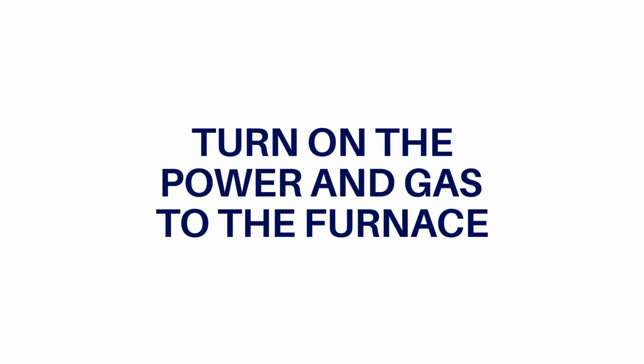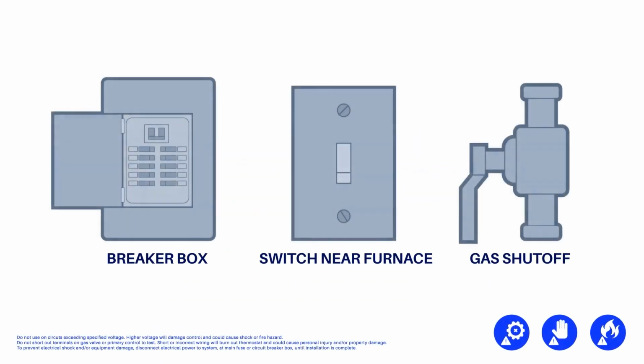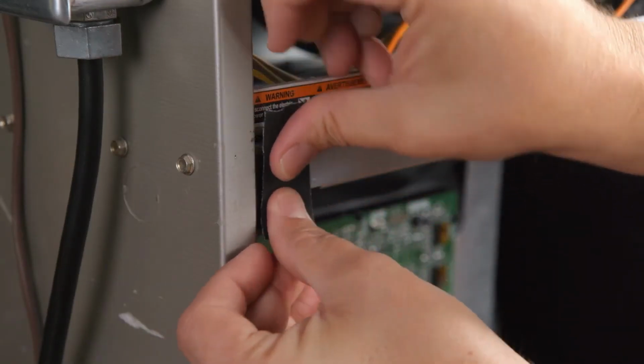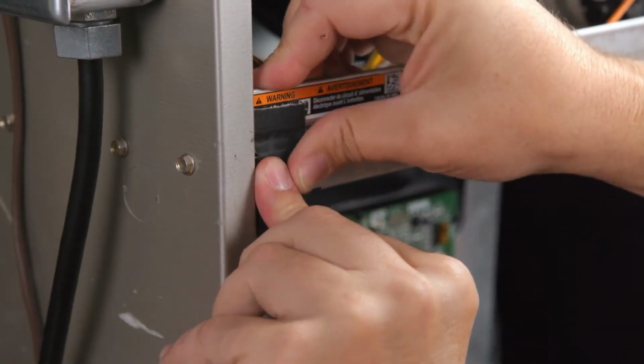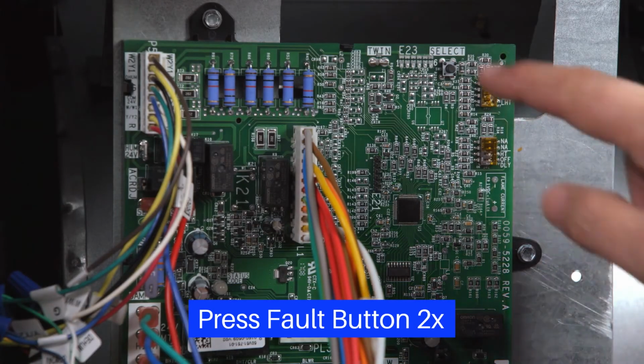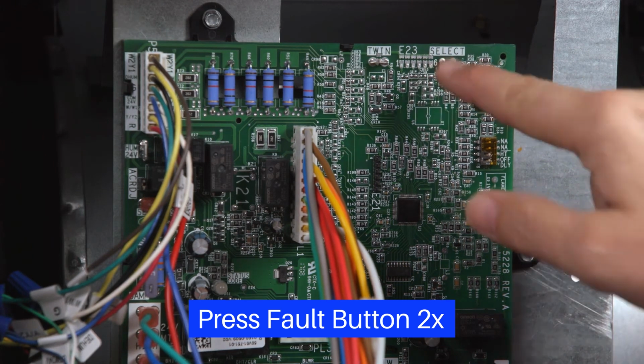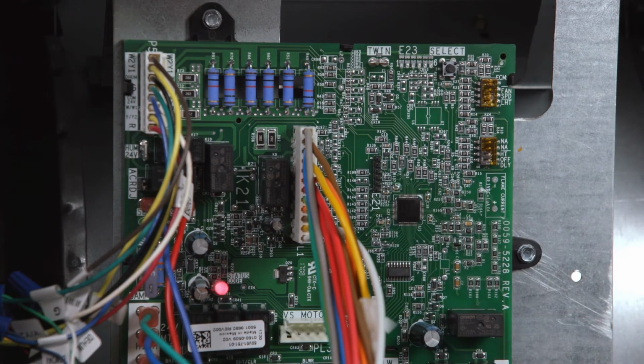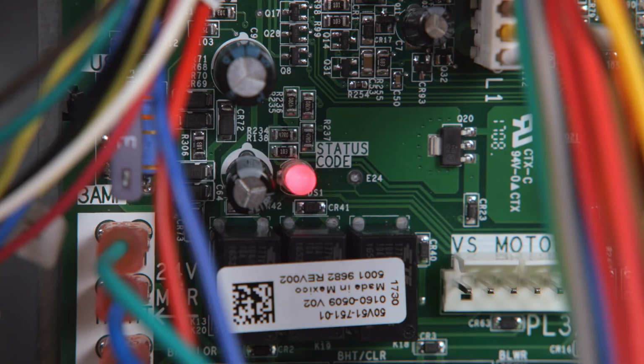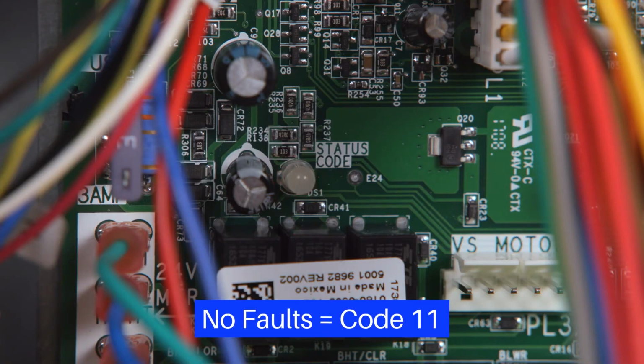The system is now ready to be tested. Reconnect electric power and gas to the unit. To enter self-test mode, turn on power and ensure the door switch is engaged. Press the select button twice within 3 seconds after powering the control. If there are faults, the control LED will flash in red the last error code only. It will do this 4 times. If there are no faults, the LED will flash 1 short and 1 long red flash 4 times.